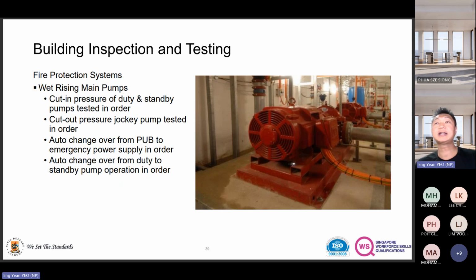Repeat again. If the cut out on the jockey pump nameplate is 180 psi, but you look at the pressure gauge and it reads 150, nothing moves. What should you do? Anyone? This is something very practical. You will face this problem, I tell you. Check the pressure switch. Usually there's one or two pressure switches. You will need to check the pressure switch as well as what? What has gone wrong during this kind of observation?